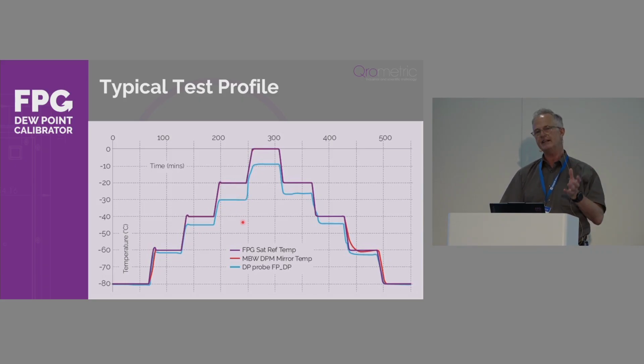And this is a fairly typical dew point sensor. They can be optimized for performing well in a certain range, so it's a way of identifying where that instrument is working very well. And as you can see here, we go from -80 back to -80 over a period of about 500, 600 minutes. So 10 hours, you can do a high and low calibration on whatever instrument you want to work with.